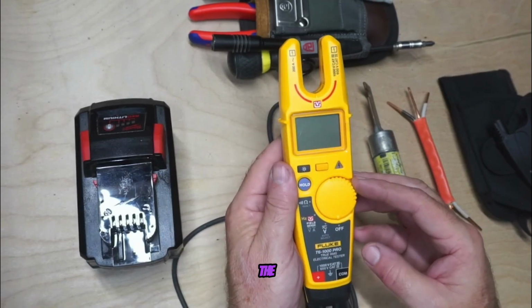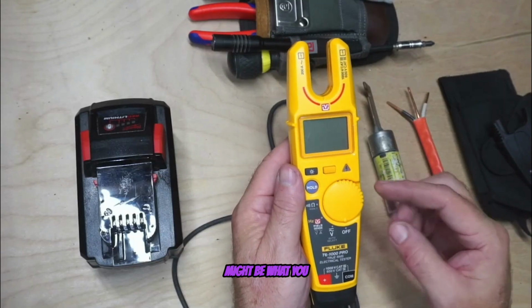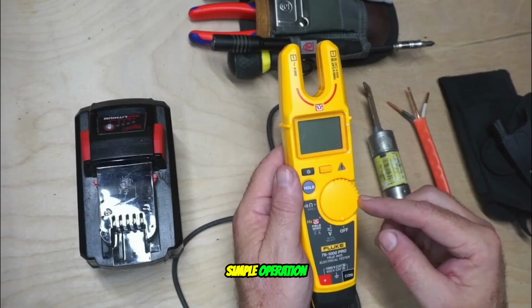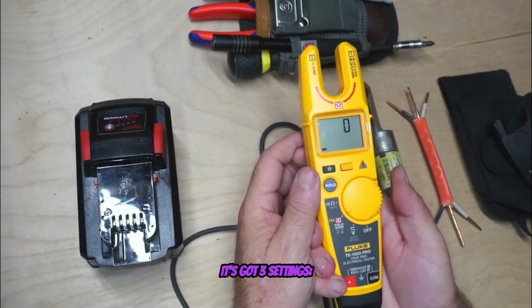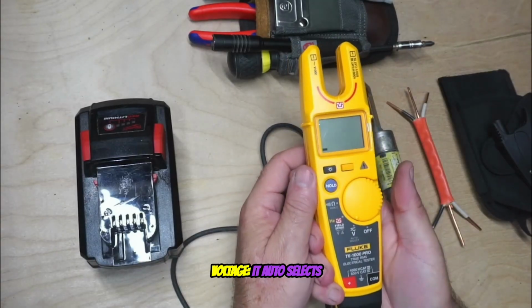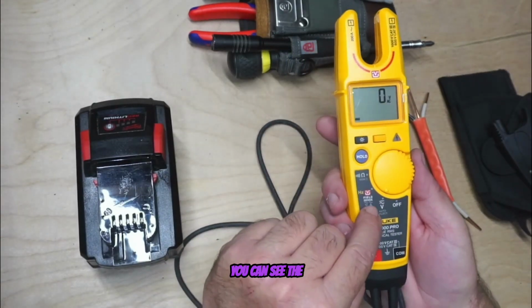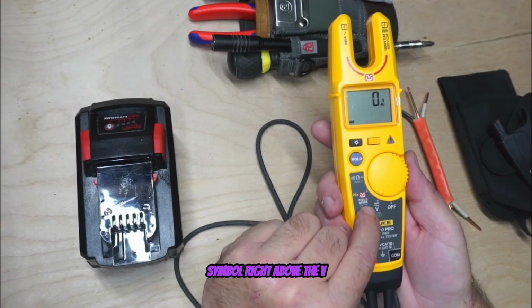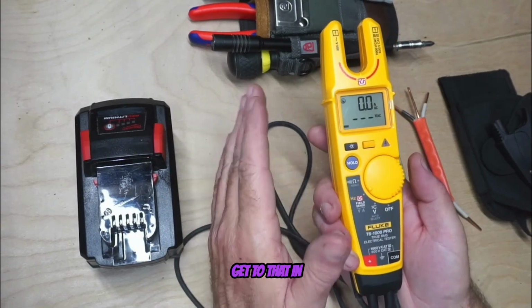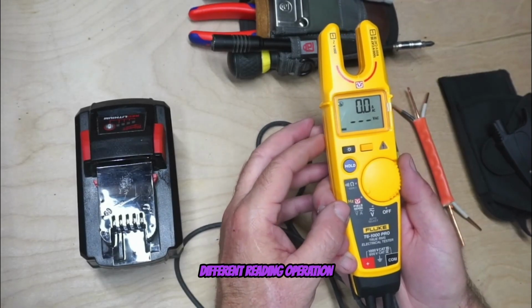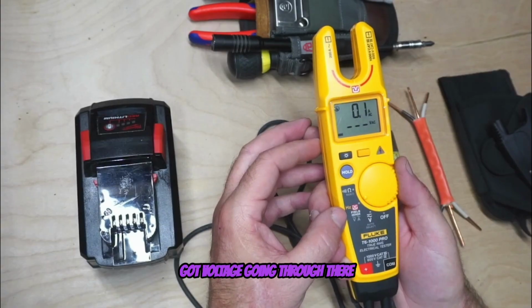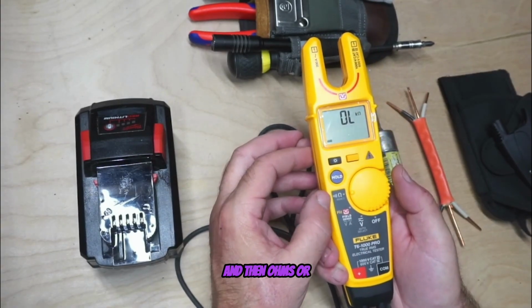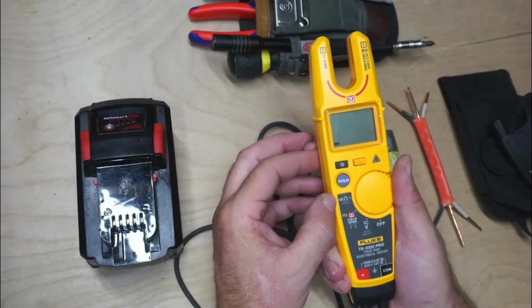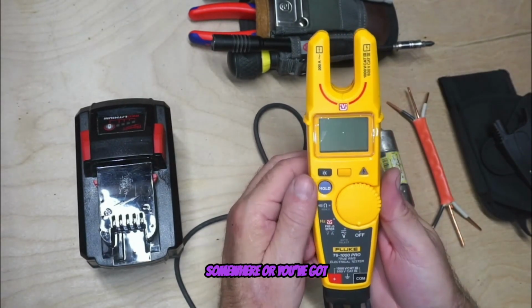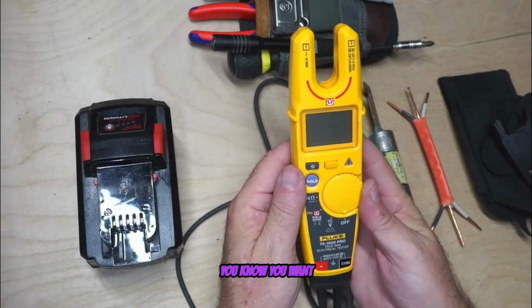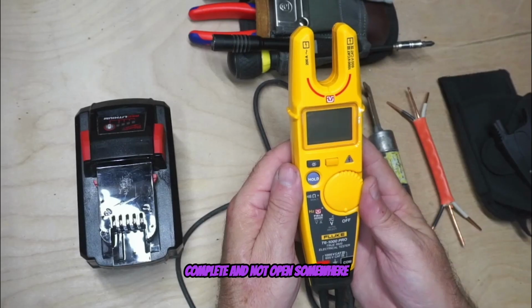So the Fluke T6-1000 Pro might be what you need. Simple operation - this dial has 3 settings. Voltage, which auto selects AC or DC - you can see the AC and DC symbol right above the V. Field sense, I'll get to that in a second - that's a different reading operation that gives you more information than just whether you've got voltage going through. And then ohms, or resistance and continuity, for when you want to check if a wire is broken or a fuse is working, making sure your electrical circuit is complete and not open somewhere.